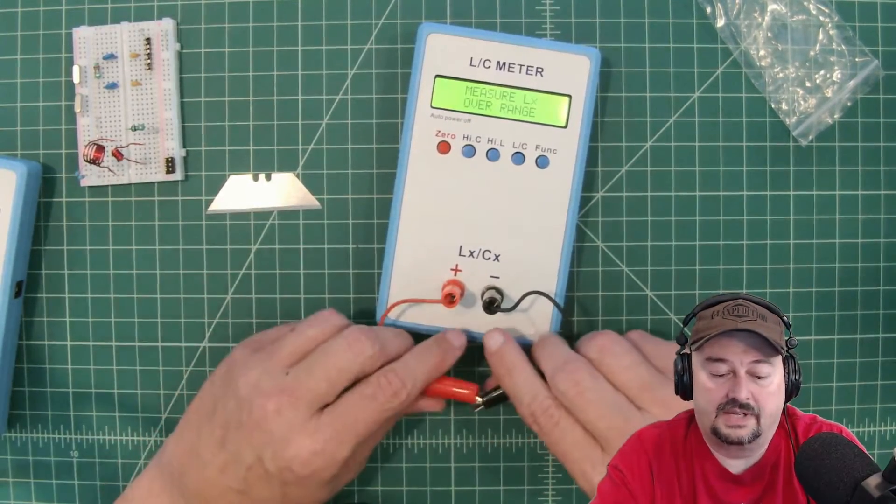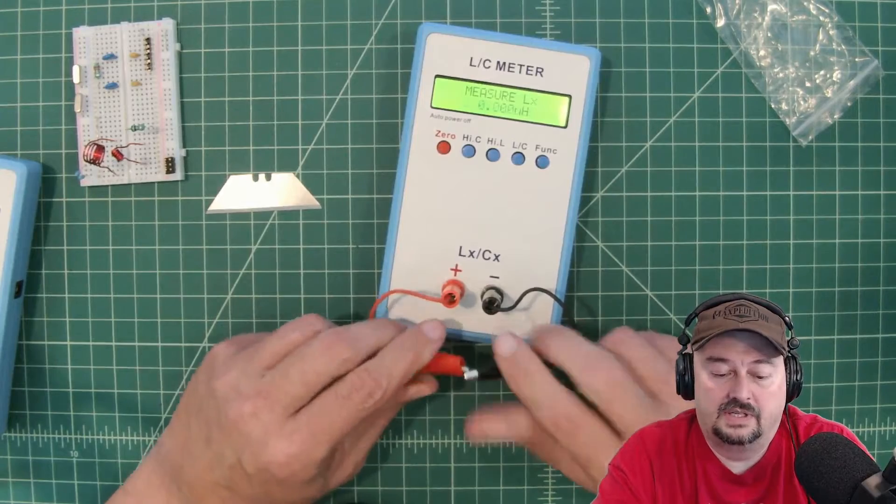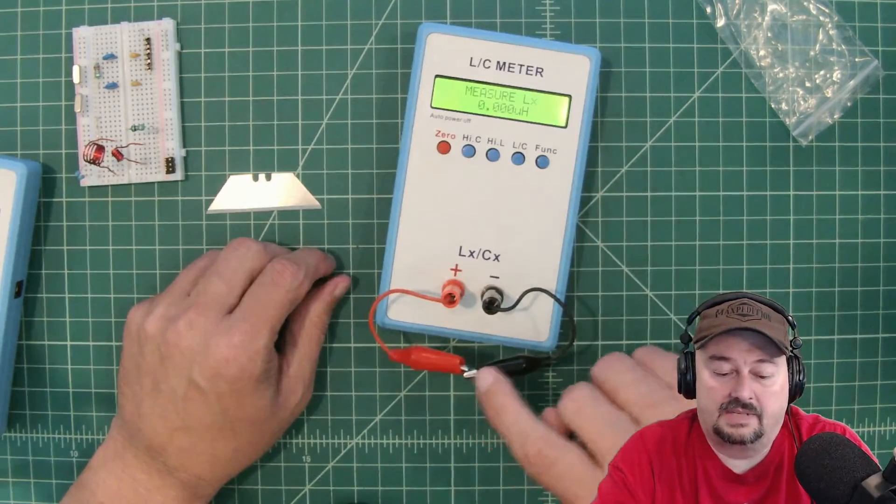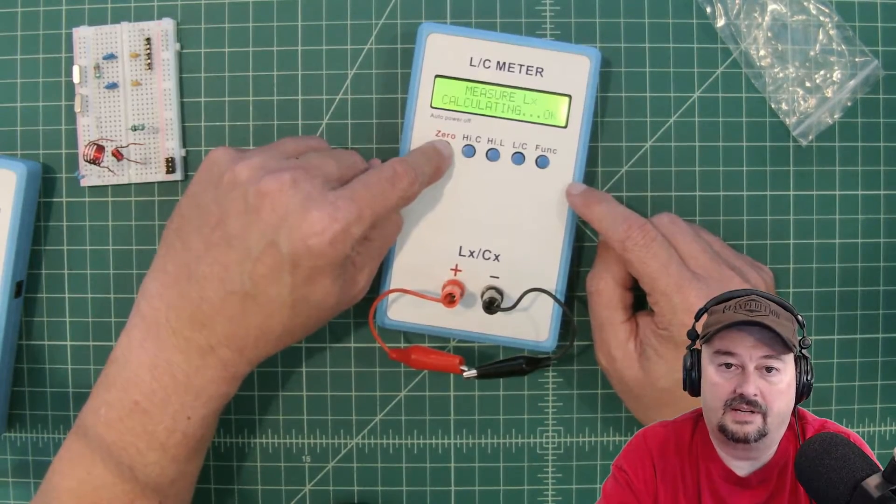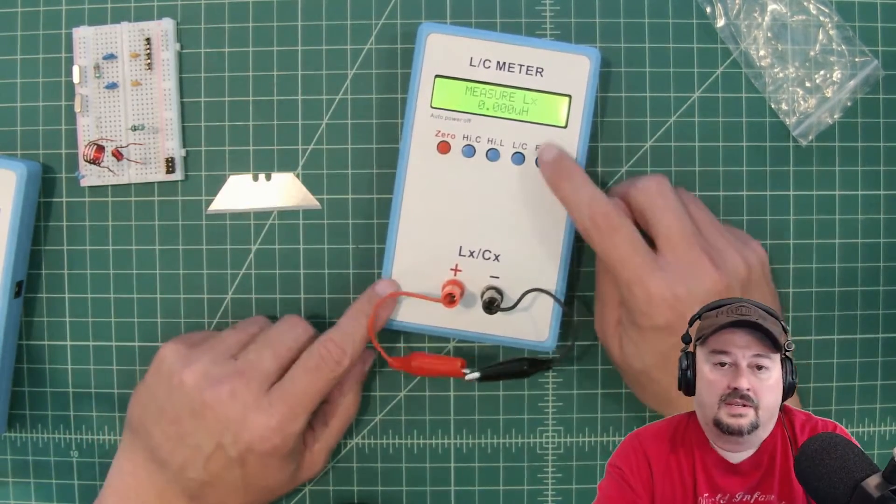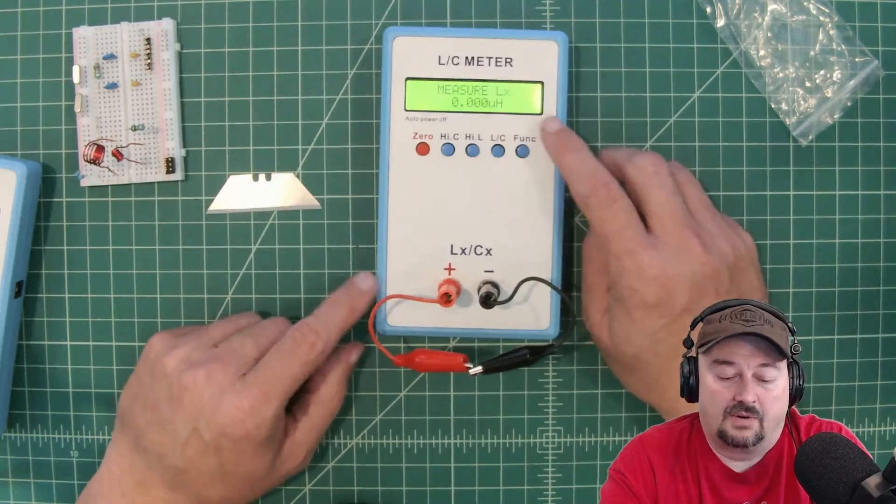And right now we're overranged. And for inductance, when you run your calibration, you want to actually make sure that these are connected. And we're already at zero, but we're just going to go ahead and recalibrate anyway. So here we are at zero microhenries.